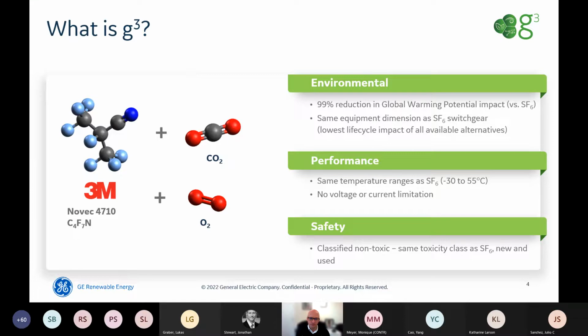To oversimplify, it's first and foremost CO2—80% CO2, 5 to 15% O2, and the rest is Novec 4710 fluoronitrile. All in all, because there's less weight, we achieve a 99% overall equivalent GWP reduction, with the same size of equipment and the same temperature range.